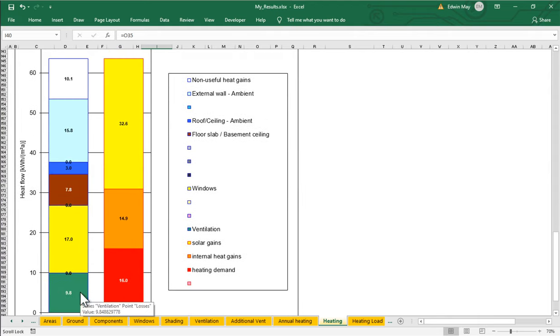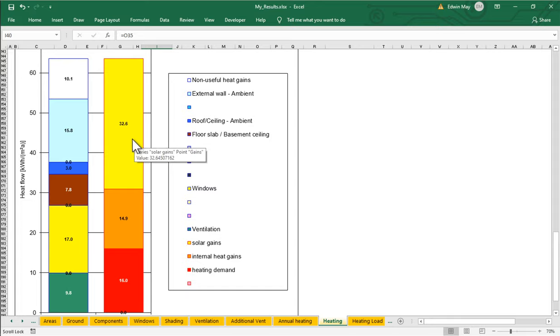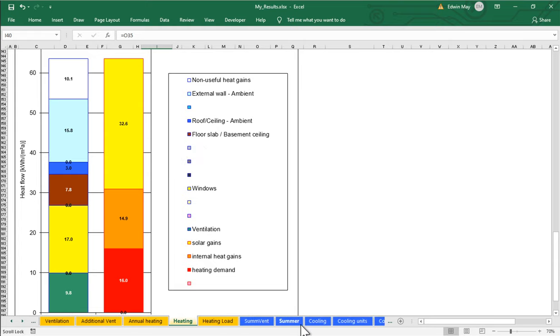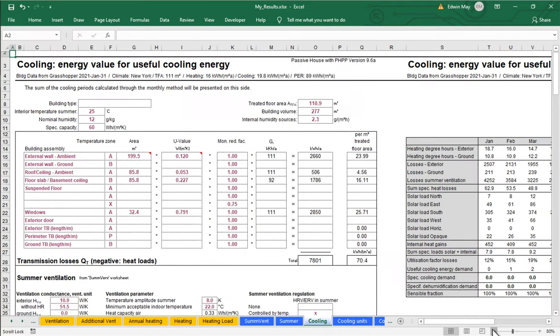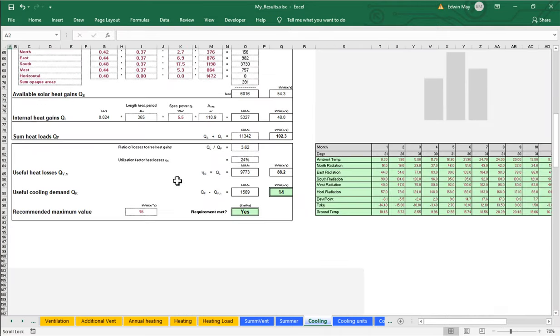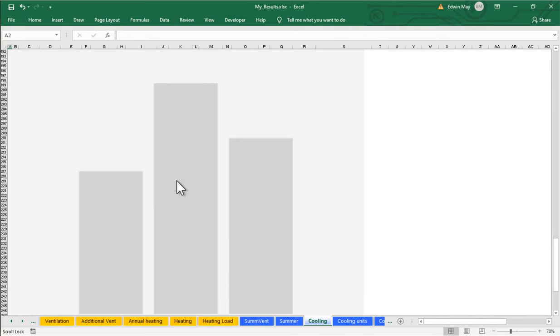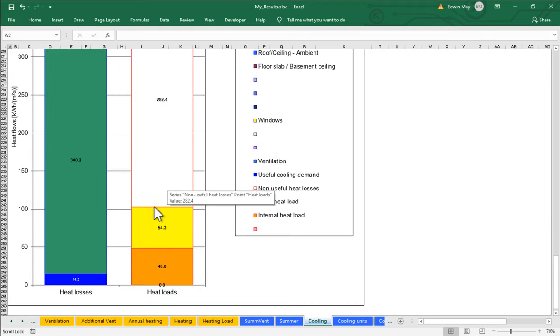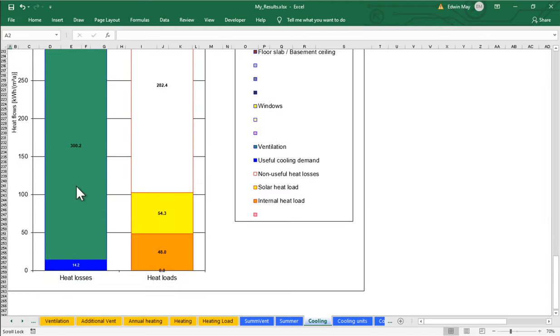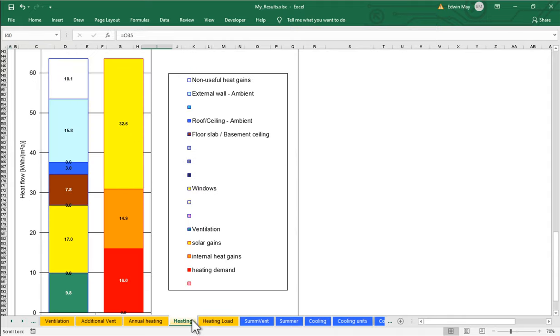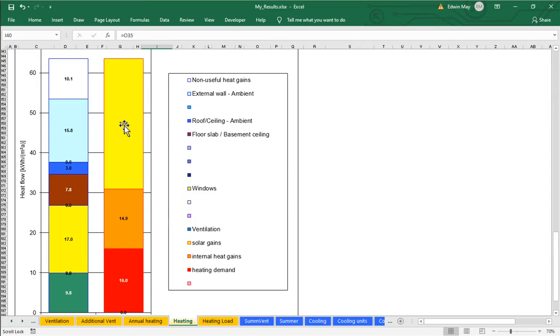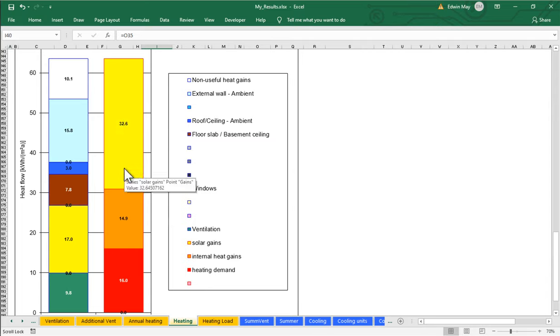Go back to our annual heating energy demand worksheet. What's the other thing? So we fixed our ventilation. We take a look at windows. The windows are seemingly not doing too well. What's the other thing that really jumps out at me about this is look at how high our solar gains are on the heating side. I wonder if they're the same on the cooling side. Let's take a look at our cooling side. Let's take a look at annual cooling energy demand. Scroll down. See our little graph. There's our operable ventilation. So 54. That's pretty high. That's still pretty high. So our solar gain appears to be pretty high to me. That's the other thing that kind of jumps out at me from this.